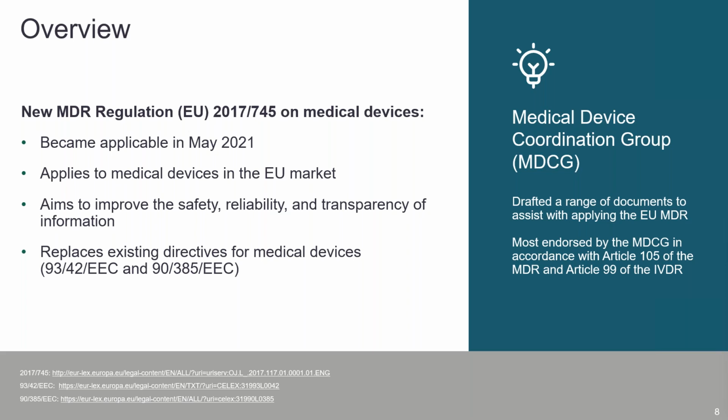The new MDR regulations on medical devices became applicable in May 2021 and are meant to improve the safety, reliability, and transparency of information for medical devices in the EU medical device market.